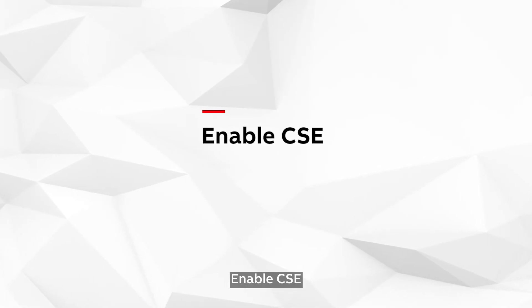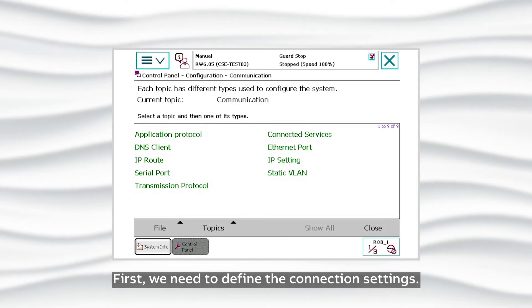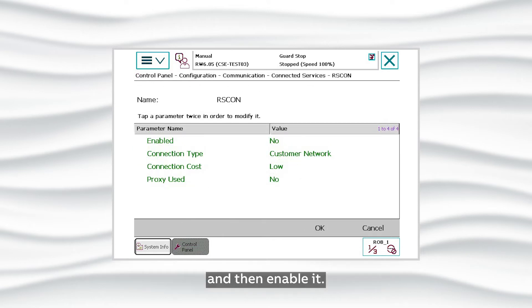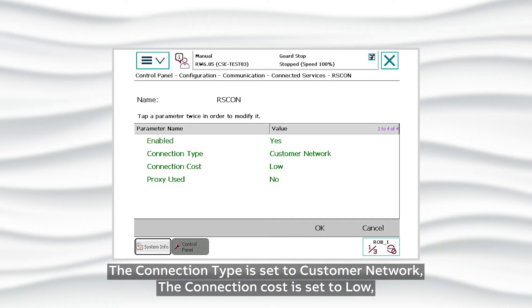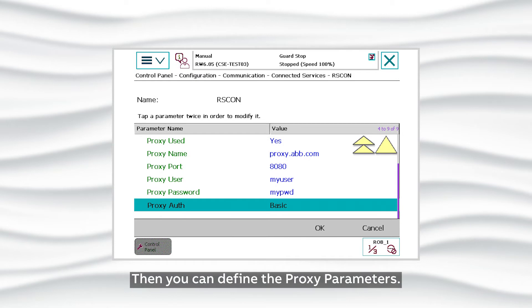Enable CSE. First we need to define the connection settings. Go to the Control Panel and in the Topic Communication, select Connected Services and then enable it. The connection type is set to Customer Network, the connection cost is set to Low, and if you have a proxy you need to enable it here and then define the proxy parameters.